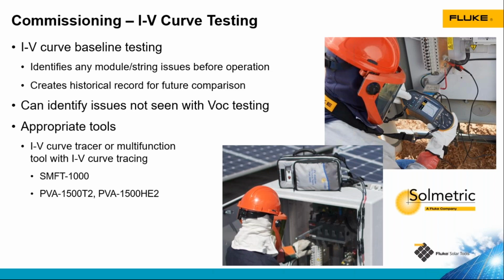And then we have the 2 PVA models. The 1500 T2 can test up to 1500 volts and 30 amps. If the efficiency of the module exceeds 19%, the current rating drops from 30 amps to 10 amps, and that's to ensure that we don't overheat and damage the test tool.